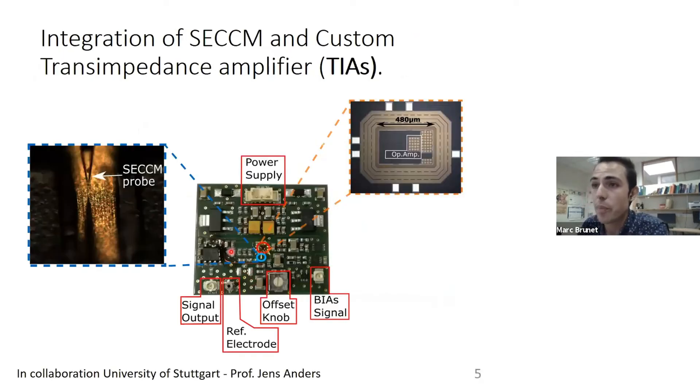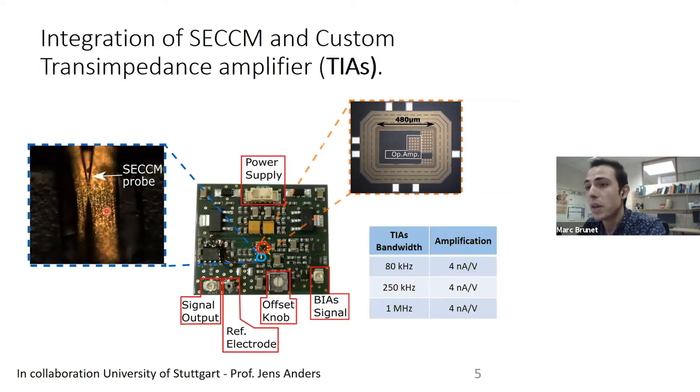Here is a picture of the PCB board that has been designed and fabricated by our collaborators at the University of Stuttgart. This PCB board has all the electronics needed to run the current amplifier. It has a current amplifier chip and also the gold electrode pad where we land our pipette and conduct our electrochemical measures. We have manufactured three of those current amplifiers with different bandwidths: 80 kilohertz, 250 kilohertz, and one megahertz, all having an amplification magnitude of 4 nanoamps per volt.